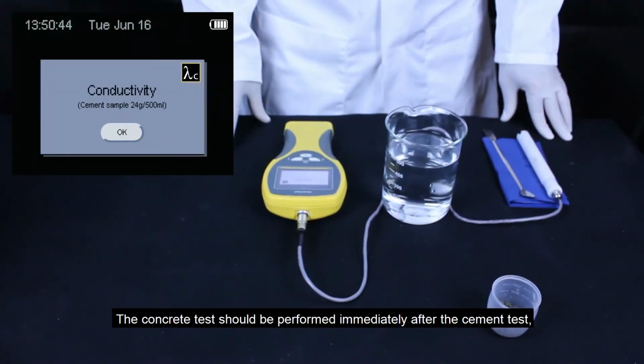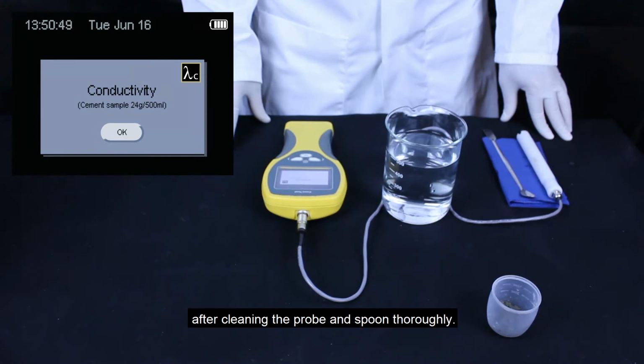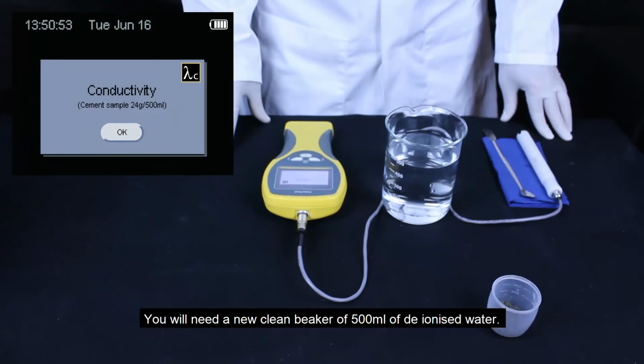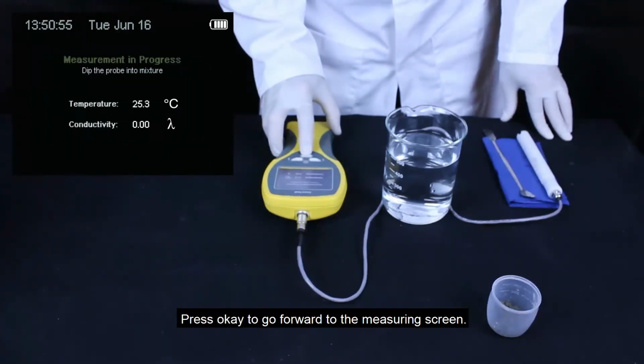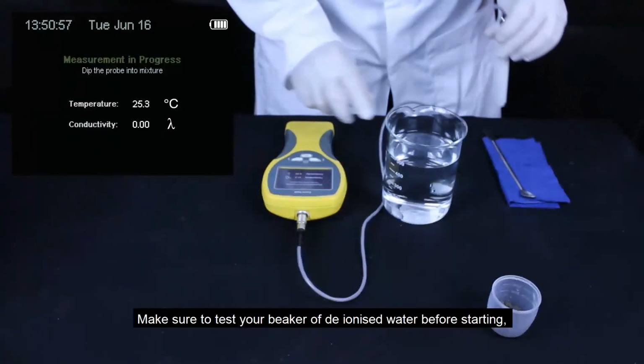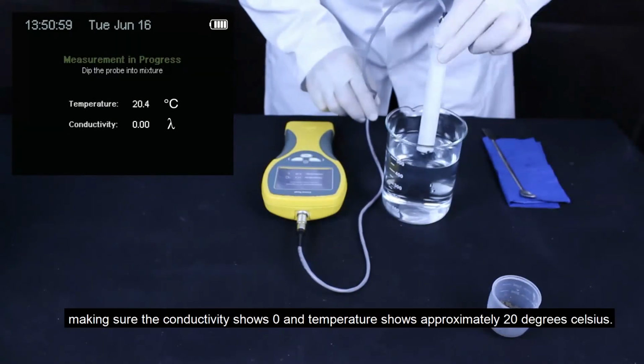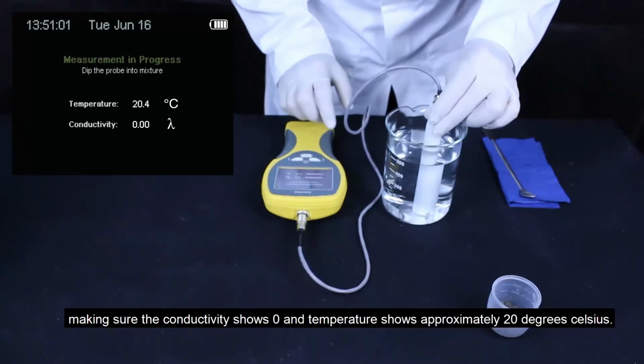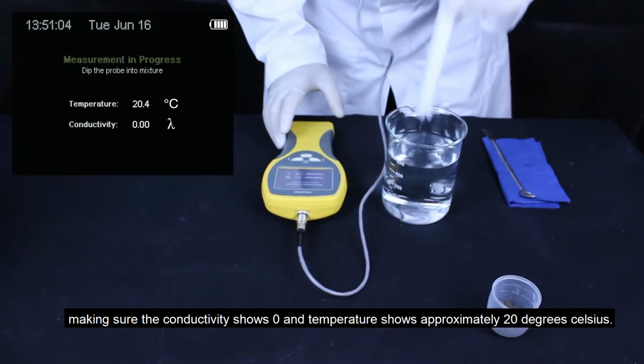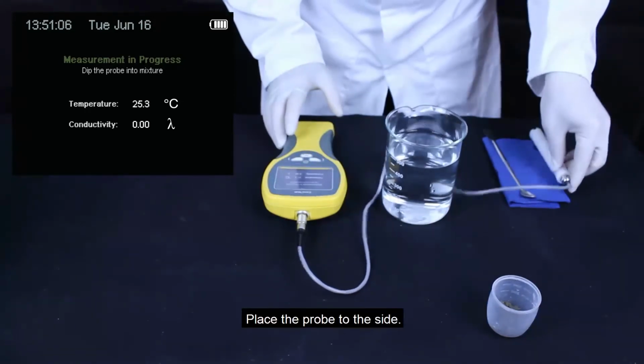The concrete test should be performed immediately after the cement test. After cleaning the probe and spoon thoroughly, you'll need a new clean beaker of 500 ml of deionized water. Press OK to go forward to the measuring screen. Make sure to test your beaker of deionized water before starting. Make sure the conductivity shows 0 and temperature shows approximately 20 degrees Celsius. Place the probe to the side.